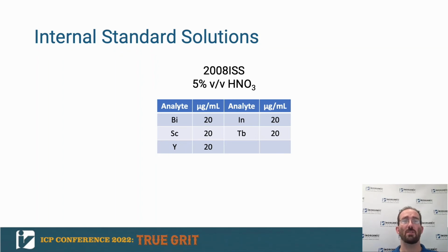Indium does have 2 major isotopes that we can look at on the mass spec. Its major mass of 115 only has a minor interference from tin-115, which is not an analyte of interest in this testing. Mass 113 does have some issues with cadmium, but we have found in our lab that 115 gives solid enough data that we don't even need to worry about the interference on 113.